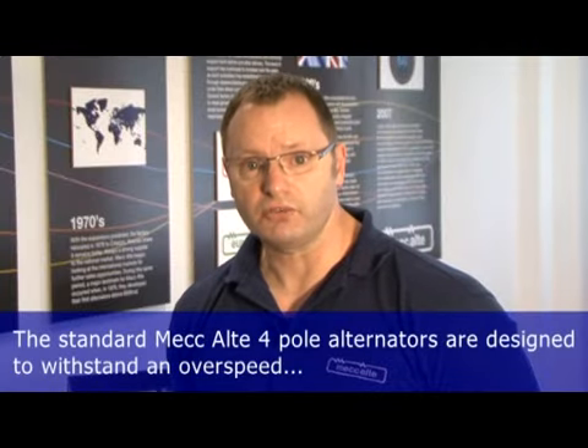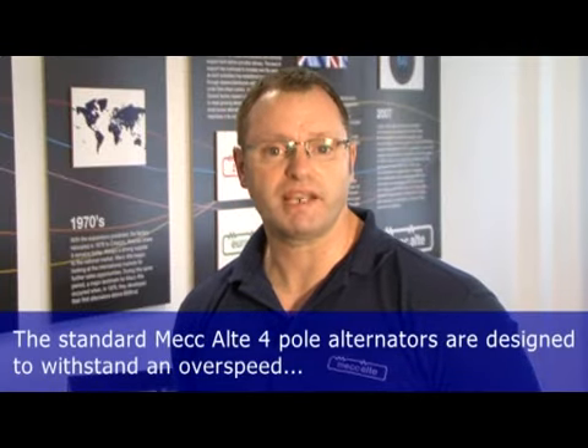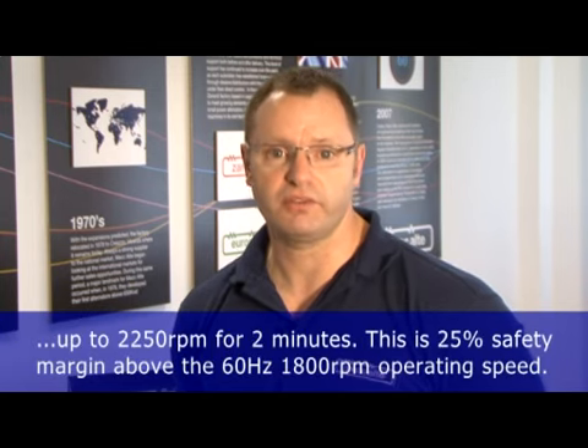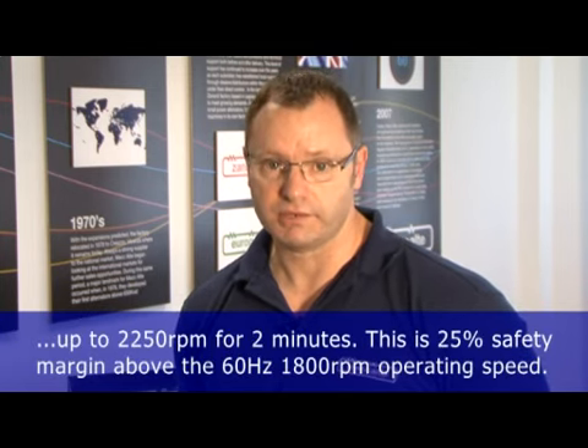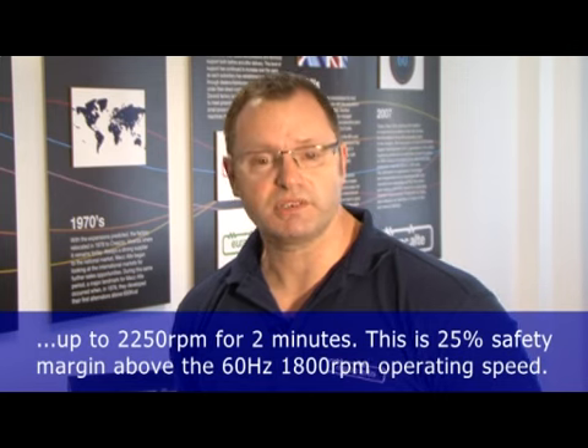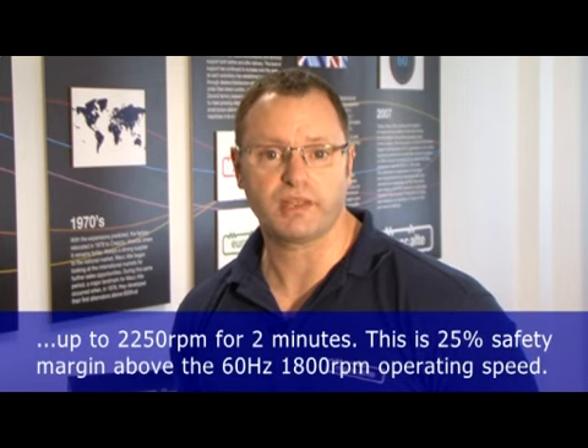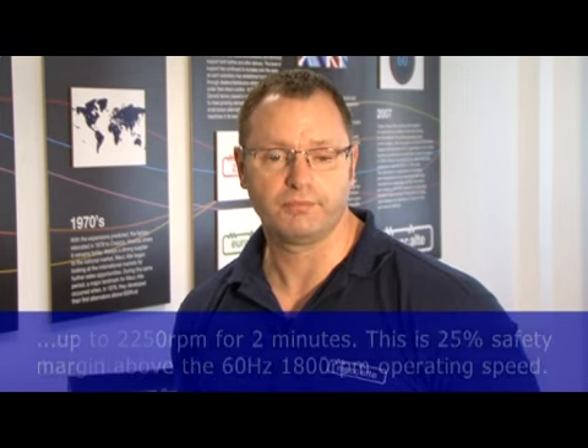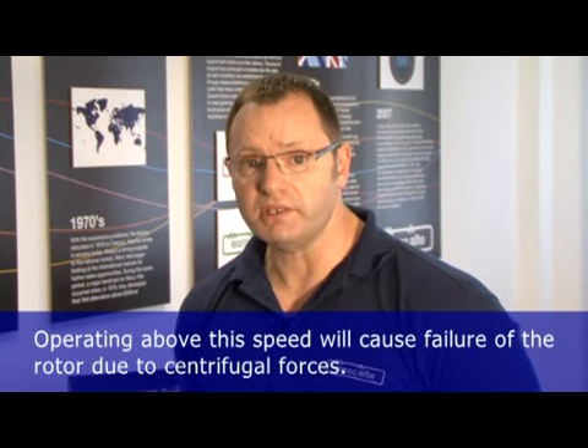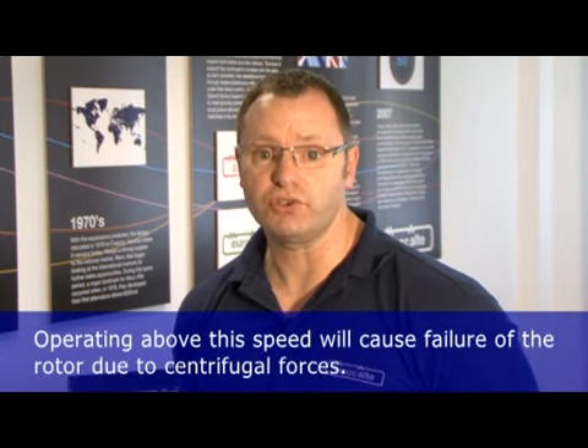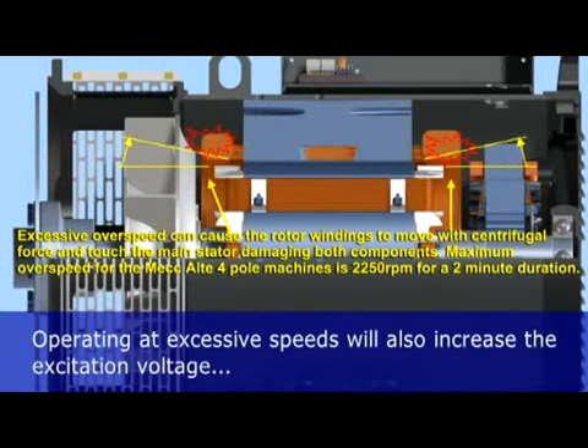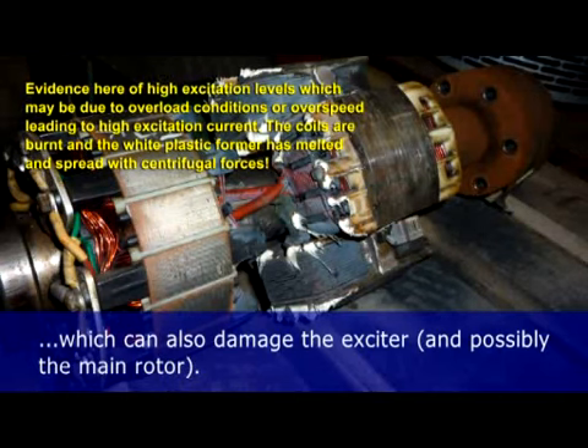The standard Mecc Alte 4-pole alternator is designed for a maximum overspeed of 2,250 RPM for 2 minutes. This is 25% above the 60 Hz 1,800 RPM speed. Operating above this speed will cause failure of the rotor due to centrifugal forces. Operating at excessive speeds will also increase the excitation voltage, which can also damage the exciter.